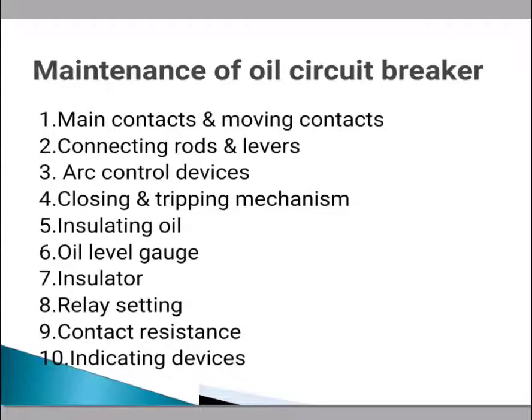For oil circuit breaker contacts, check the moving contacts and fixed contacts. File the contacts with a smooth file if badly pitted, clean them with emery cloth and then fine cloth. If the contacts are burned, replace them. This is carried out quarterly for heavy duty and yearly for normal duty.